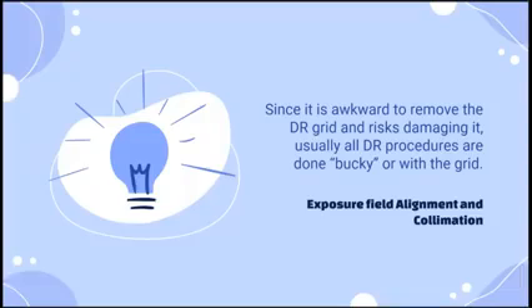Since the receptor plate is worth millions, you'll be risking damaging it. Okay, so we just won't remove it, and then we'll do every single examination, no matter what the anatomical part or thickness, in bucky or in grid, which results in increased patient dose for the patient. Okay.